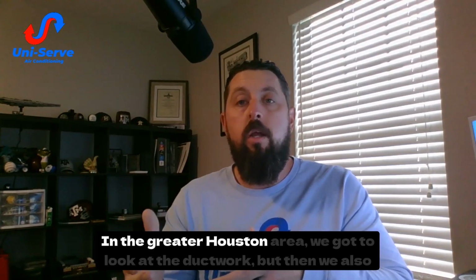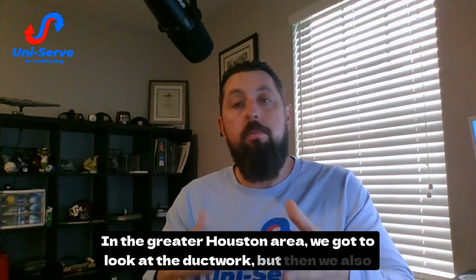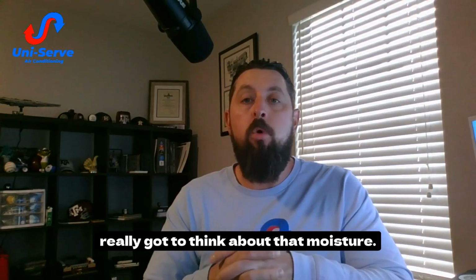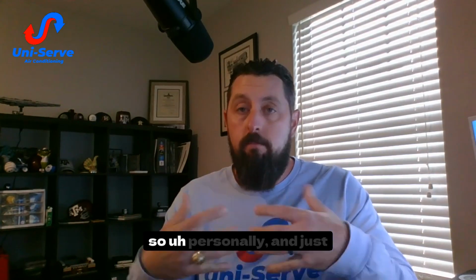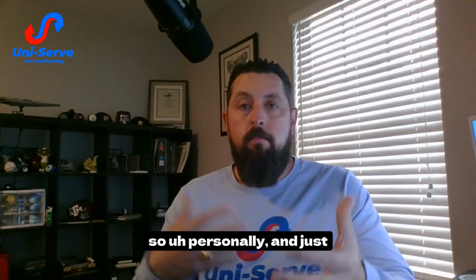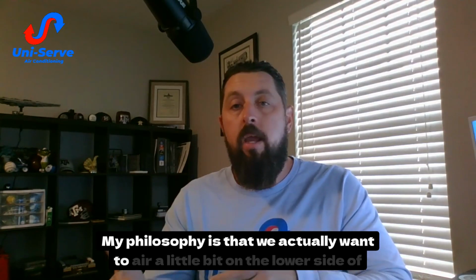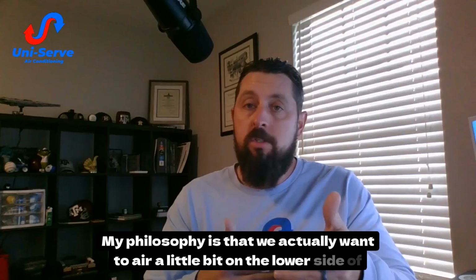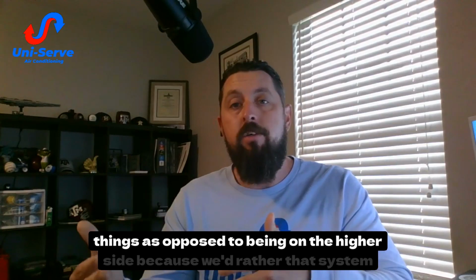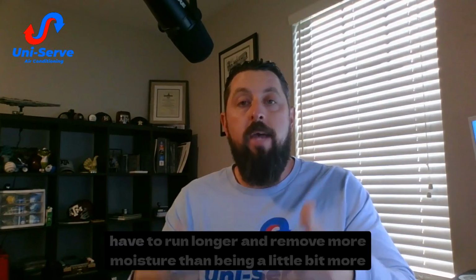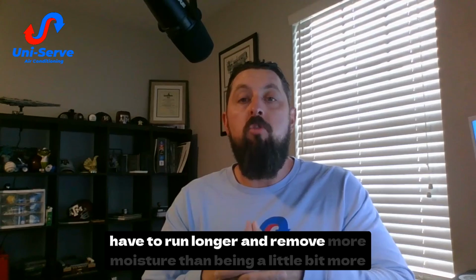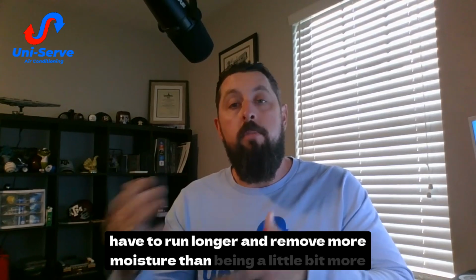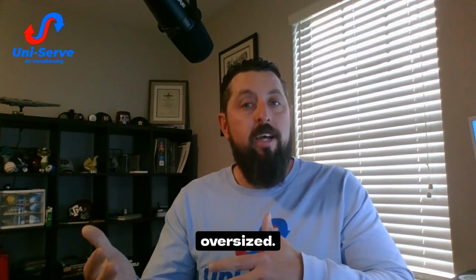In the greater Houston area, we've got to look at the ductwork, but then we also really got to think about that moisture. So personally, my philosophy is that we actually want to err a little bit on the lower side of things as opposed to the higher side, because we'd rather that system have to run longer and remove more moisture than being a little bit more oversized.